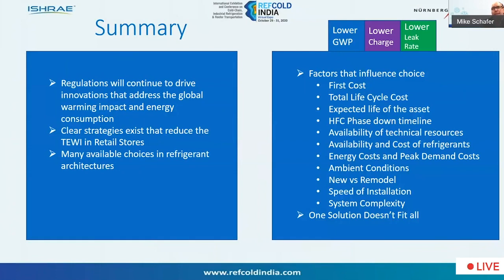Certainly the expected life of the asset in terms of the investment. The HFC phase down timeline would also play a role. Then the system complexity, the availability of technical resources, the availability and cost of refrigerants, energy costs and peak demand costs. I didn't really talk about peak demand costs, but situations exist where there's a high peak demand that has demand charges that also come into play in terms of the system. And then the climate conditions play a role in consideration for any of these types of systems. New versus remodel, and then obviously the speed of installation all come into play. And the one thing that's pretty clear is that one solution doesn't fit all applications, so all these things must be considered and the trade-offs made.